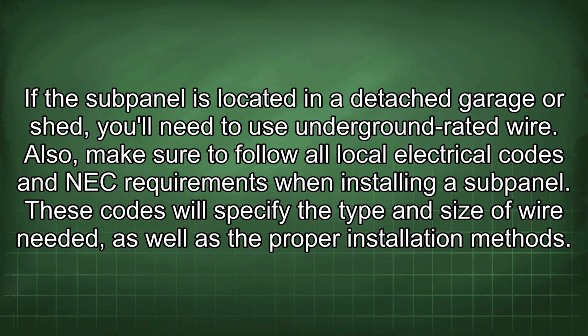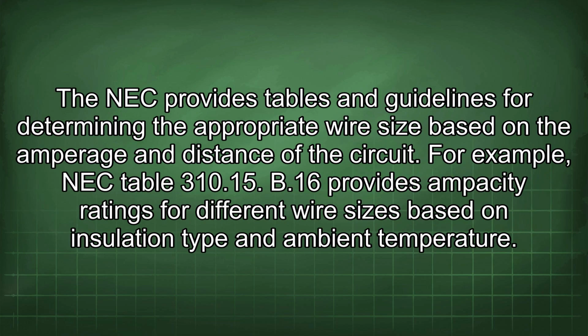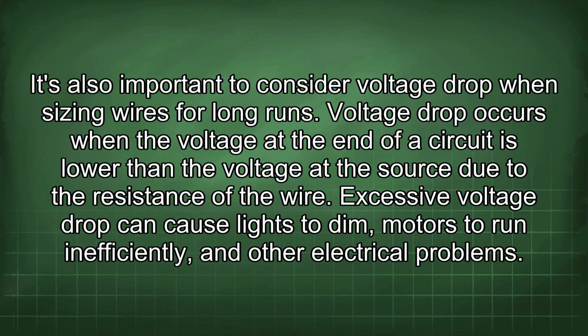Also, make sure to follow all local electrical codes and NEC requirements when installing a subpanel. These codes will specify the type and size of wire needed, as well as the proper installation methods. The NEC provides tables and guidelines for determining the appropriate wire size based on the amperage and distance of the circuit. For example, NEC Table 310.15(B)(16) provides ampacity ratings for different wire sizes based on insulation type and ambient temperature. It's also important to consider voltage drop when sizing wires for long runs. Voltage drop occurs when the voltage at the end of a circuit is lower than the voltage at the source due to the resistance of the wire.